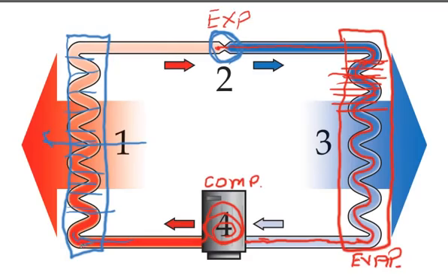So as this high pressure, high temperature gas travels through this condenser, the gas condenses into a liquid, and that's where the condenser coil gets its name as a condenser. It condenses back into a liquid, and by the time it reaches the end of this coil, it should be totally liquid. Then it travels through the copper tube back to the expansion device and starts the cycle all over again.